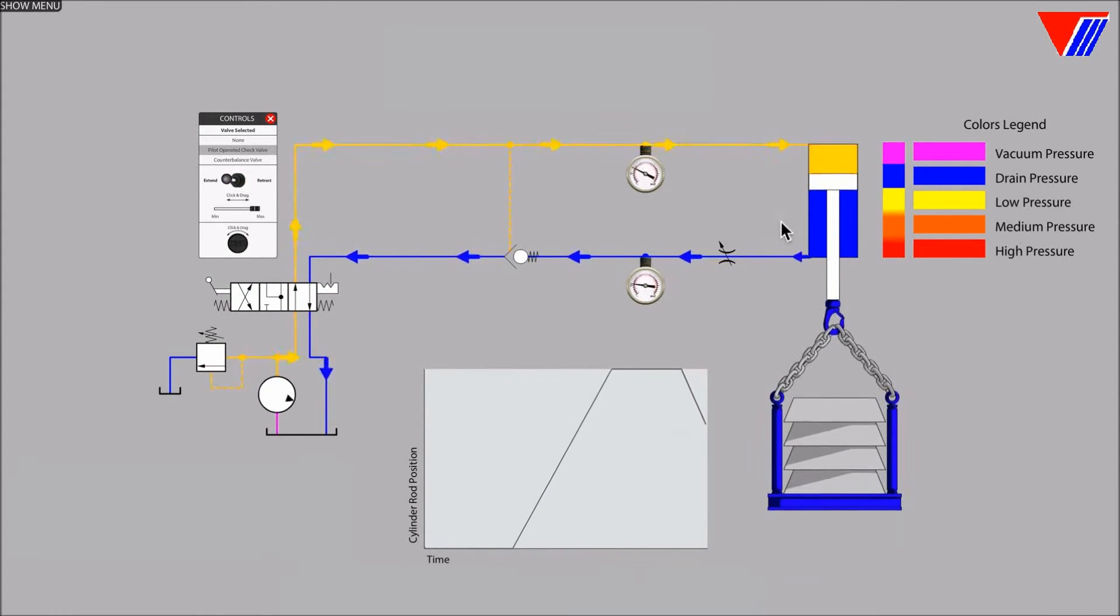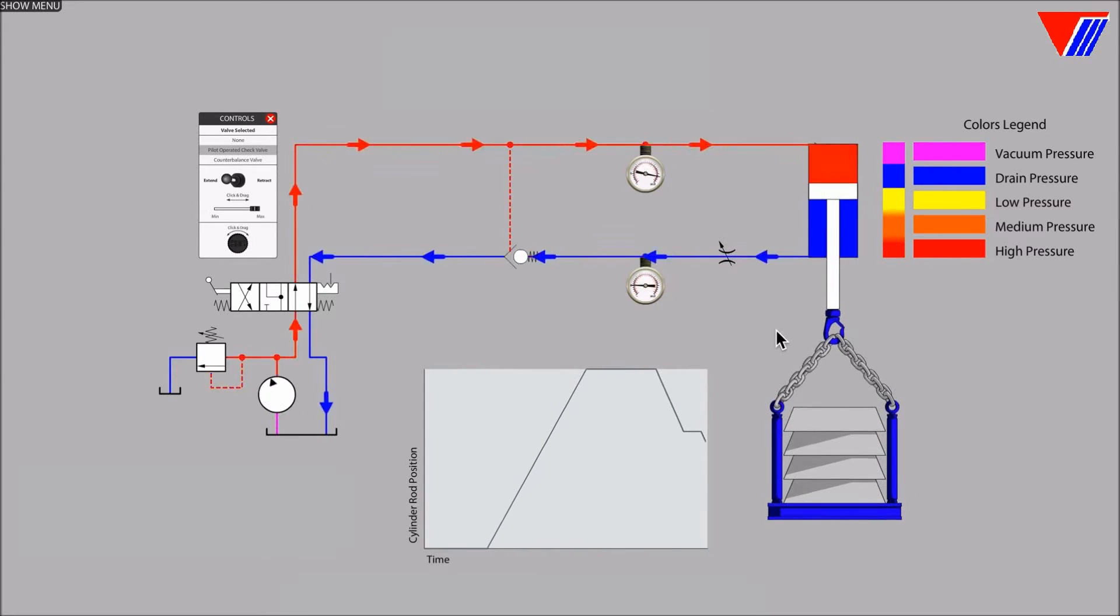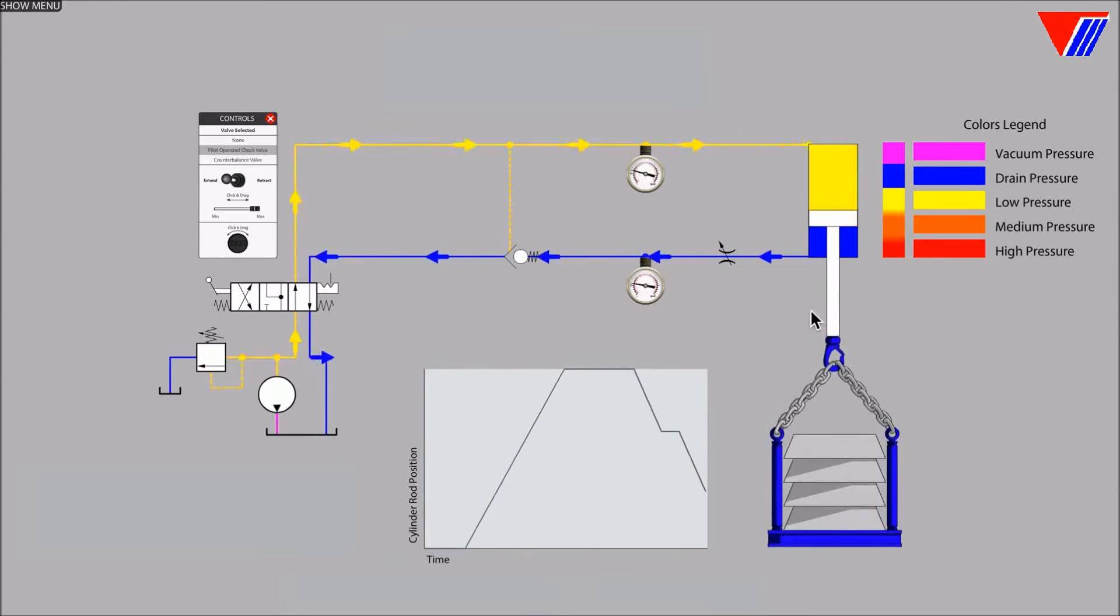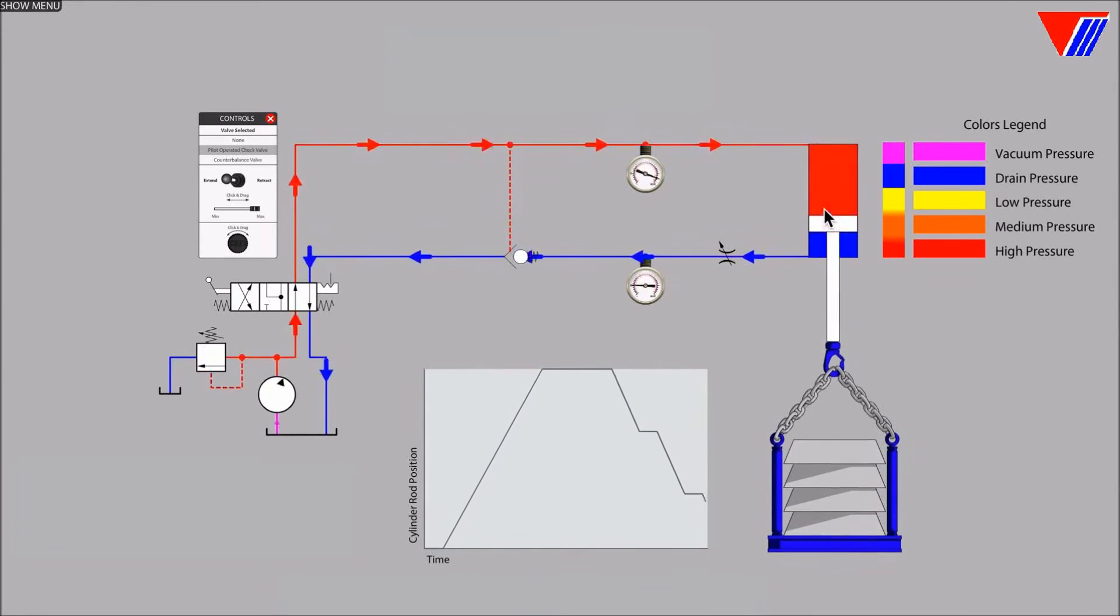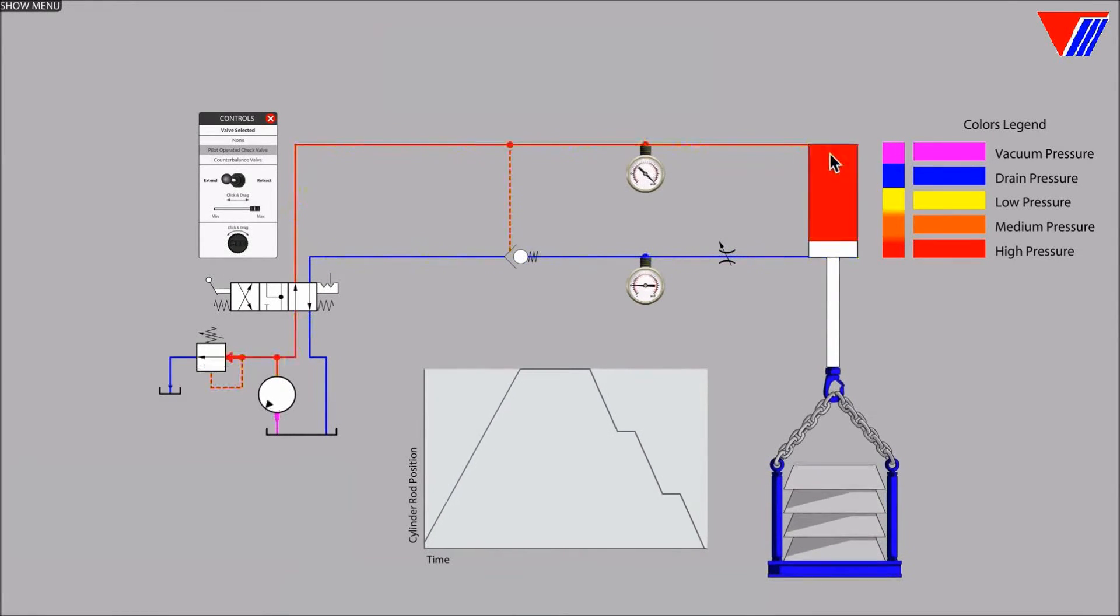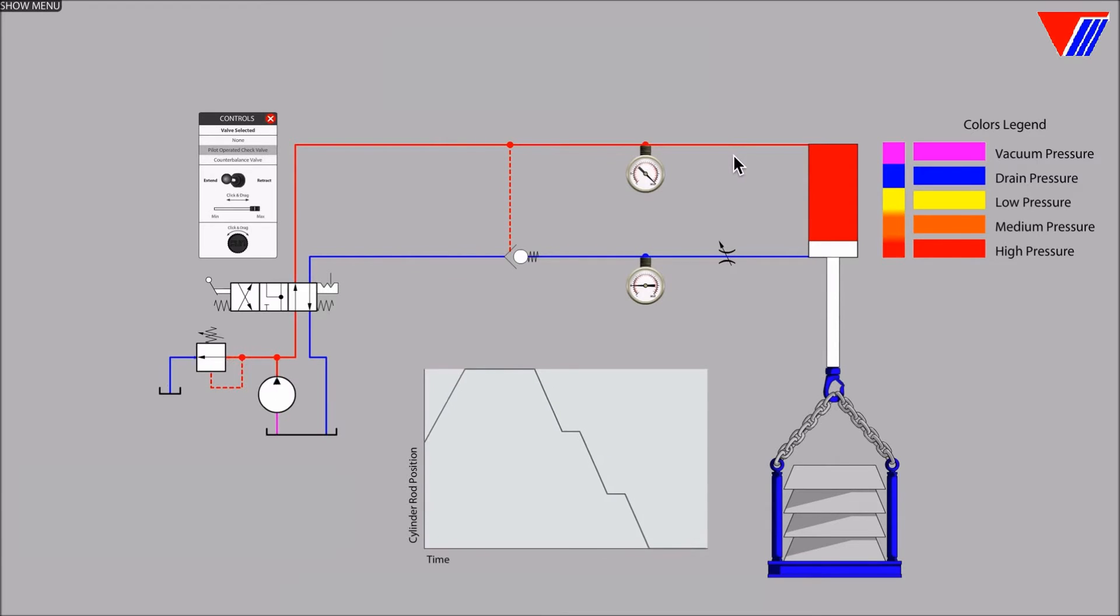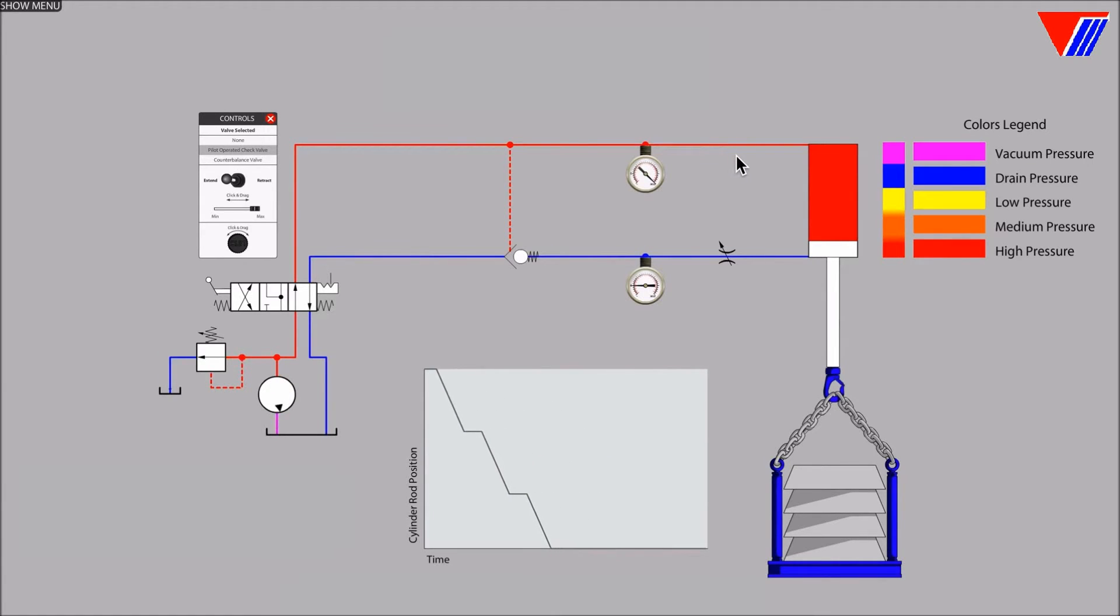As the load and the cylinder rod ran away with the help of gravity faster than the rate of fluid supplied by the pump and directional valve, the pressure in the upper cylinder line dropped to a very low level. In some circuits, the pressure may even drop into partial vacuum.